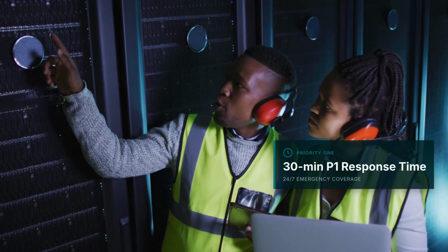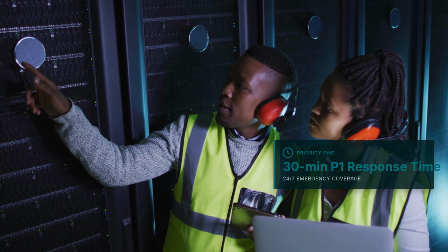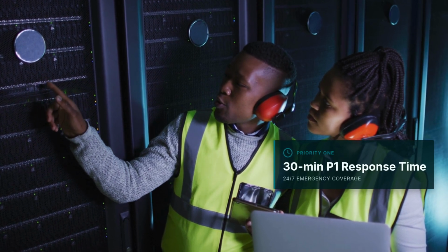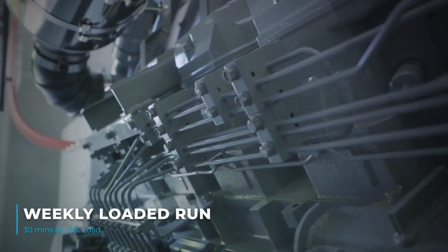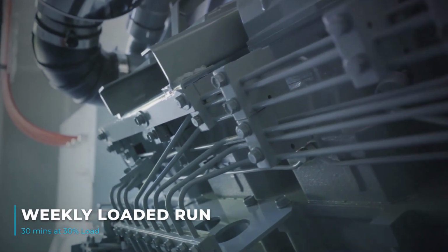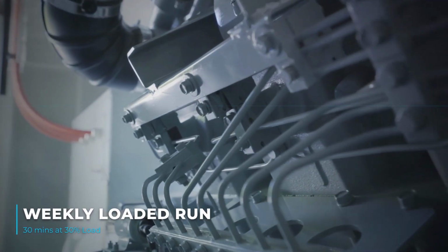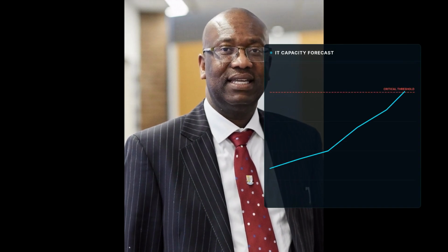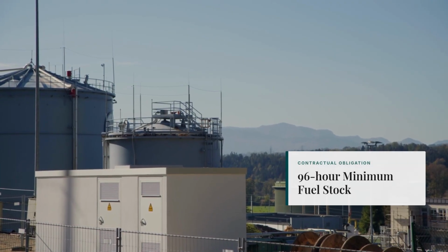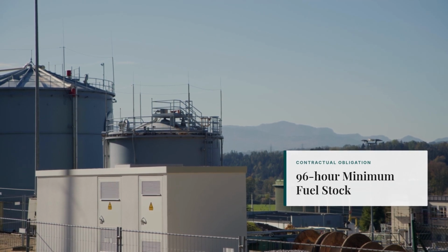In year 1 alone, DH1 requires 847 planned preventive maintenance tasks. Emergency response is strict: a 30-minute window for priority 1 alarms, 24 hours a day. All 20 generators undergo a weekly loaded run on a rolling 5-day cycle to ensure readiness. Capacity management is handled via DCIM, forecasting exactly when the next IT threshold will be hit. And we maintain a 96-hour minimum fuel stock at all times. It is a contractual obligation.